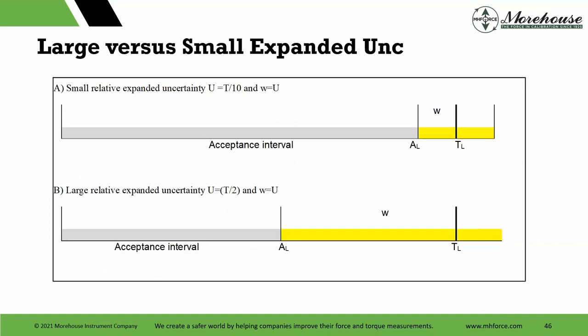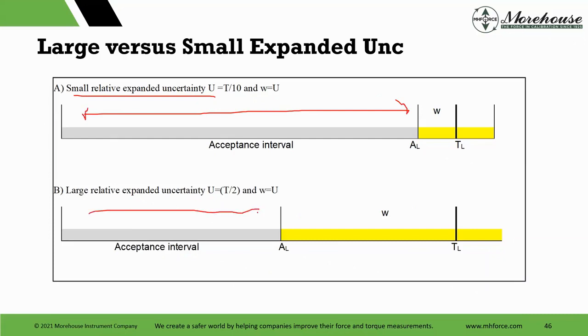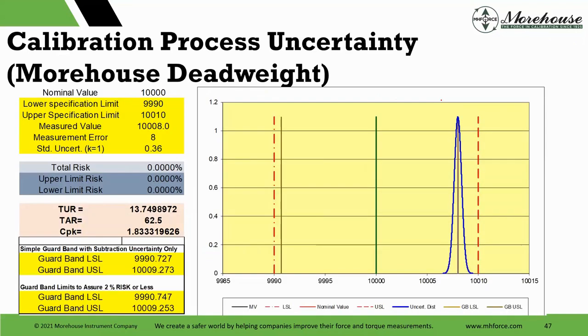So this is what it's saying, right? This picture is probably worth 1,000 words. It's basically saying I use that small relative expanded uncertainty, and my acceptance interval is a lot larger than when I use the large uncertainty. That's all we're saying. So with this, using the dead weight, I have more wiggle room from each side to be in. And we'll show that in more detail. Here's calibration process uncertainty, Morehouse dead weight, 10,000 pound cell.